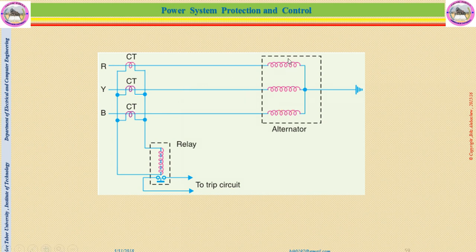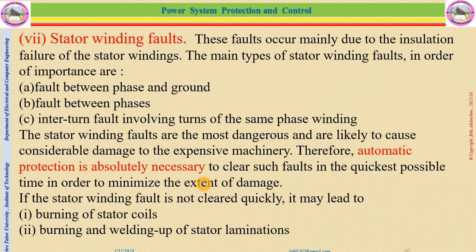So here is the generator or alternator winding. Here is the ground. If the system is balanced, the sum of the currents of phase R, Y, and B becomes zero. If some problem happens, the sum of the three currents may not be zero because they are unbalanced. If the system is unbalanced, the sum of the currents may differ from zero, so there is a current which passes through the relay coil. If this current is equal to or greater than the pickup current of the relay, it will give a signal to trip the circuit breaker. That means if the relay is energized or operates, the circuit breaker will trip the circuit from this fault.